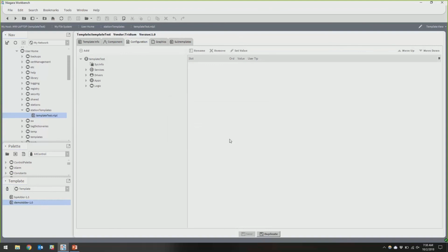That brings up a good one, a Pandora's box that I'm going to open up, that I got all excited about because I actually thought it was implemented, but I was found quite wrong. You know how in AX with JACEs, I should say non-8000s, if you forget the platform credentials, what do you do? You go into shell and you hit escape to go in and you reset, clear your credentials.